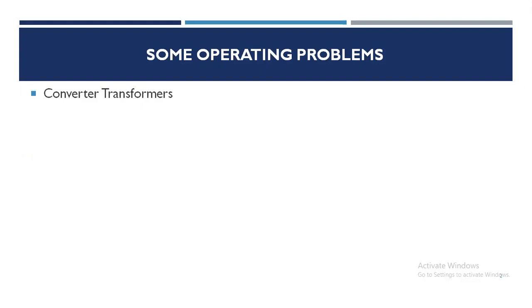According to the statistics of CIGRE, many failures in converter transformers have been occurring, although concentrated in a few HVDC projects. The major problems are in the area of turn-to-turn failures in valve side windings, leads, and clip failures. Also, DC bushing failures. Although the failure rates of converter transformers are not too far from the failure rate of AC transformers, the consequences of the HVDC converter transformer failures on the system operation are much more severe.